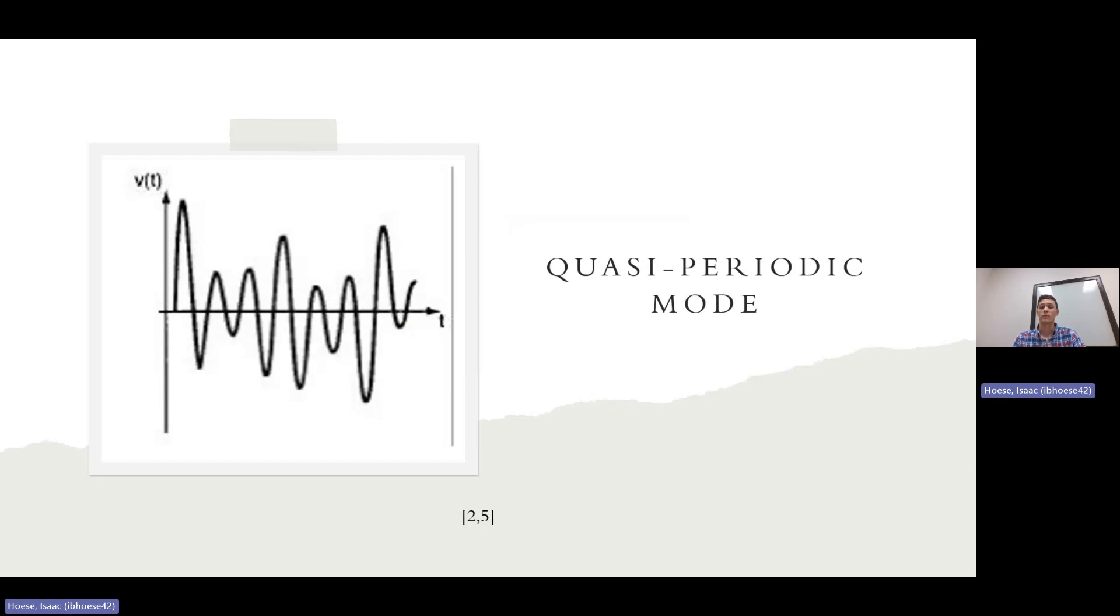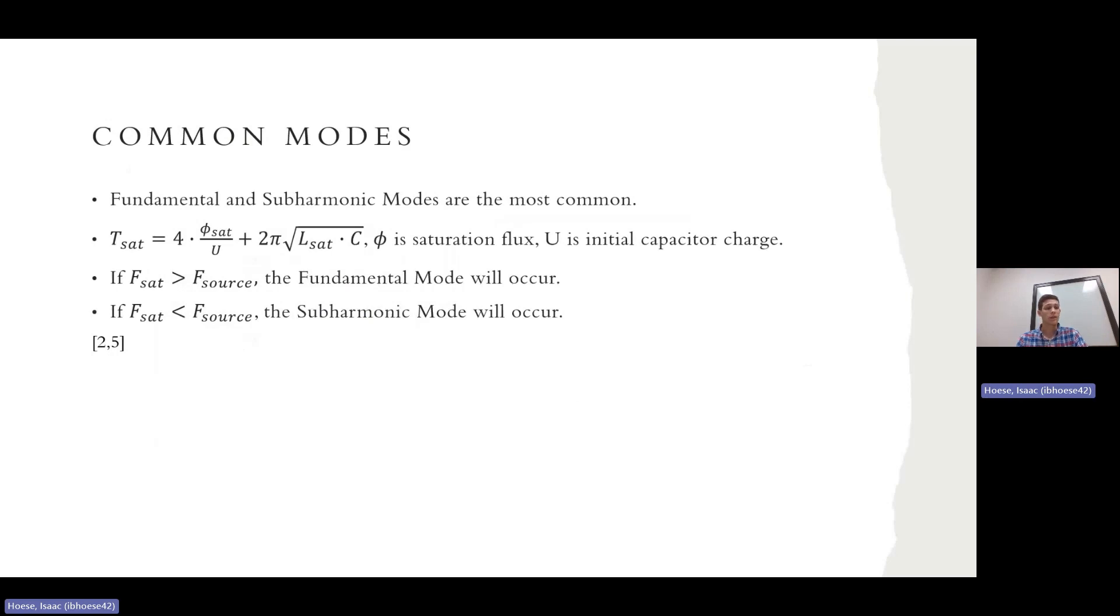The last one we have here is the quasi-periodic mode. And it has an incoherence looking at the frequency spectrum. And what I mean by that is the frequencies jump around. And in the subharmonic, they were, all the harmonics came every division of the fundamental frequency. With this one, there is no certain number. And studies have found that the quasi-periodic modes were possible in voltage transformers at a reasonable scenario. So they are possible, but not common. And that's where we see here the fundamental and subharmonic modes are the most common.